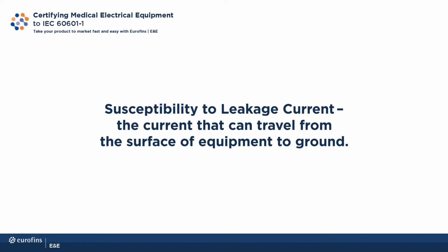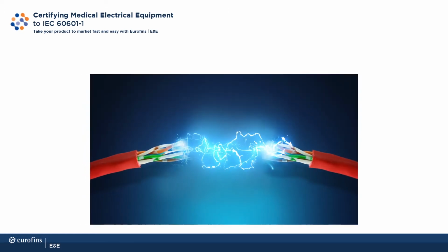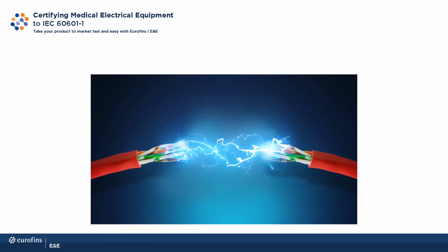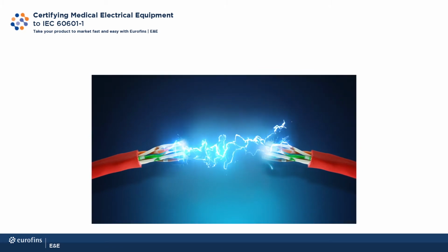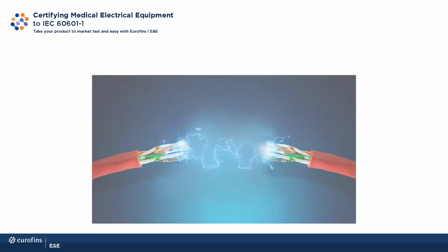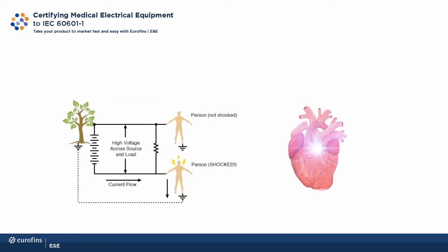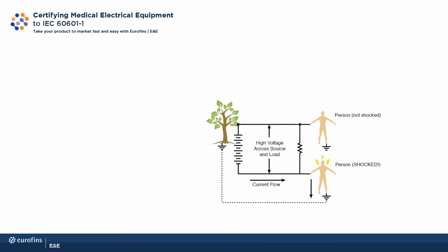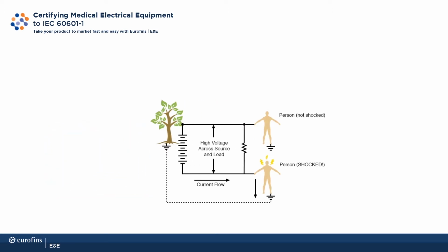Now that we've discussed the patient, let's talk for a moment about the aspects of medical electrical equipment that can harm a patient. First, we'll discuss leakage current. All electrical equipment has leakage current, even low voltage equipment. This current can travel from the surface of equipment through a person to the ground. Current generally goes from line to neutral, or from positive to negative for a battery. However, there is some leakage current that does not go through the loop. It may go through the ground wire, or it may be present on the surface of the equipment. It is accessible to anyone who touches it. If a high leakage current were to pass through the heart to the ground, it can cause death. The patient in this scenario is more susceptible because they can't call for help and can't move away.